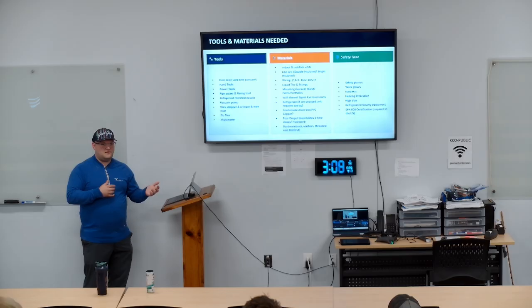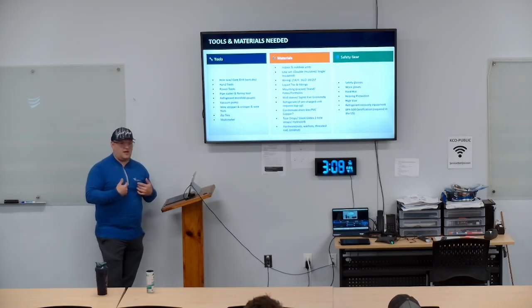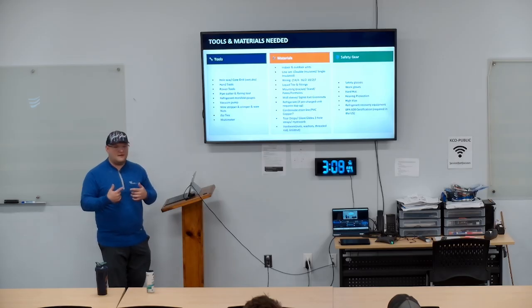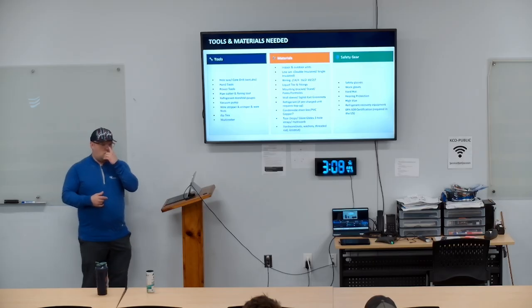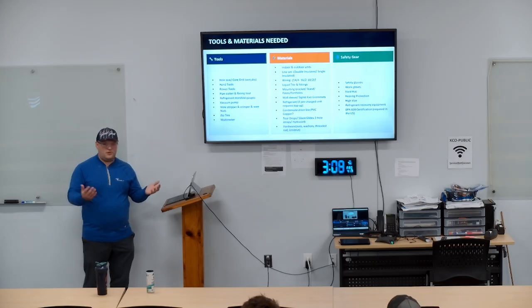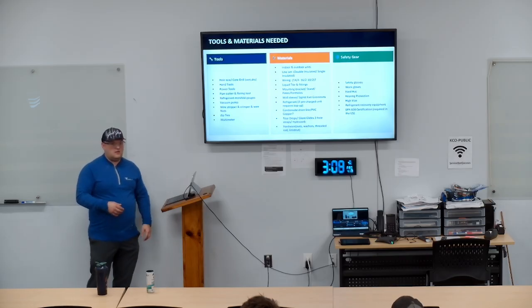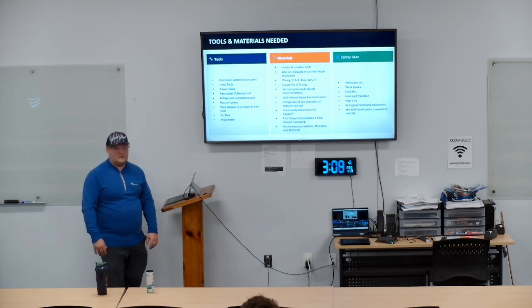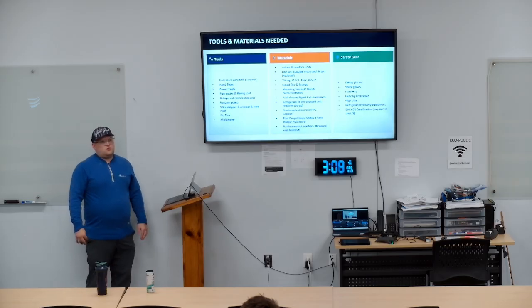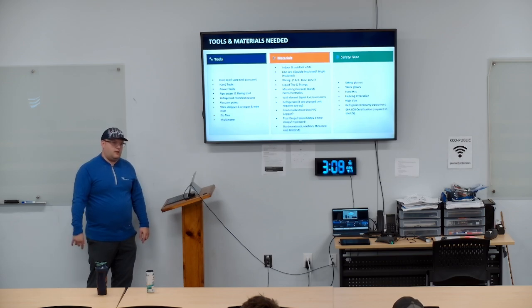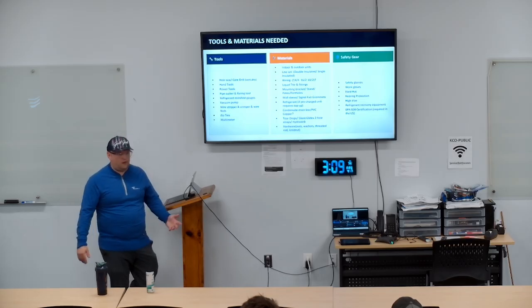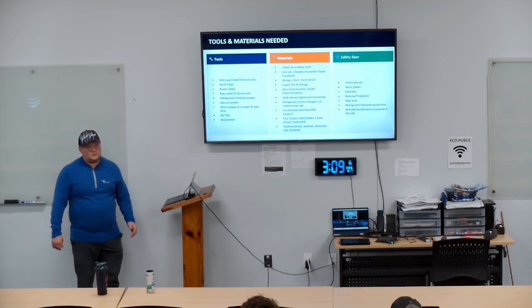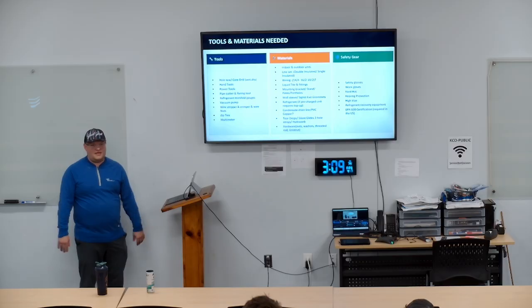Well, the problem with that is none of our pipers are running 1-1/8 in soft copper. No one wants to bend 1-1/8. It's crazy. So the difference for us now is time, because it's going to take us much longer to install hard copper than it is soft. You don't get hard copper pre-insulated. You get soft pre-insulated. So the time alters substantially for us. It almost takes twice as long to do hard copper than soft copper. So whatever their bid would be, it would be double. That's something I communicate to Dan and them regularly when we run into this kind of stuff. But that's why I go to the IOM, because you won't know unless you look at the IOMs.